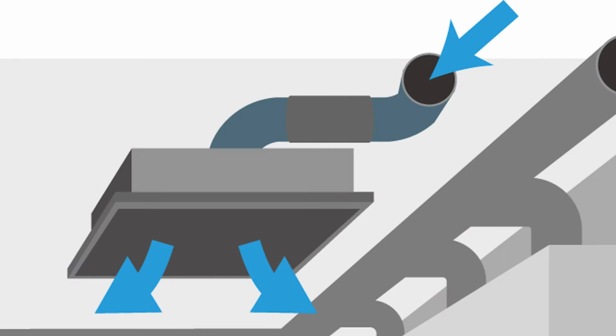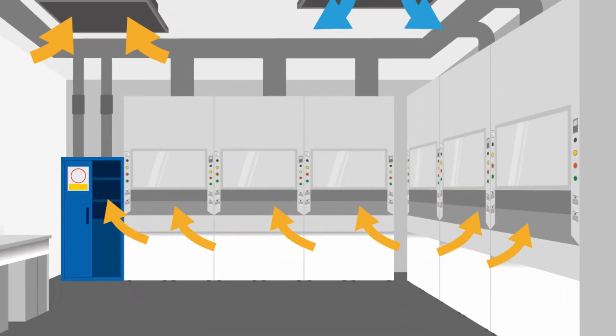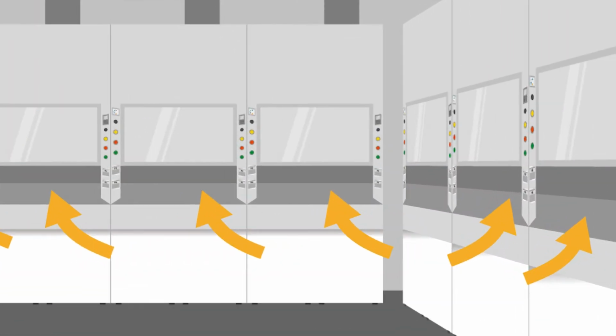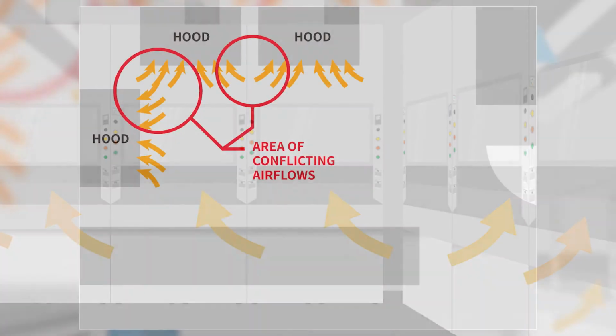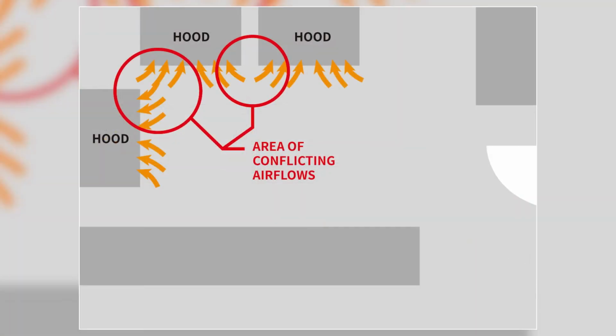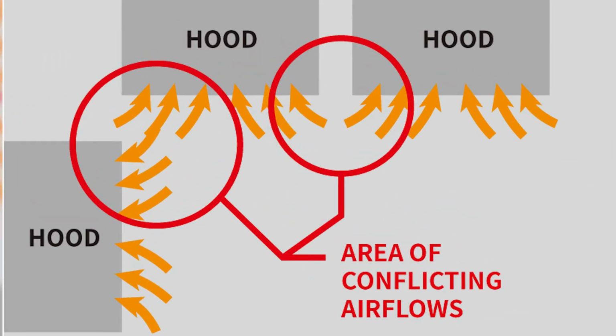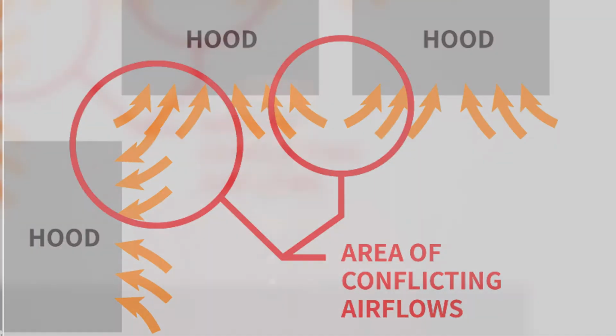Another source of turbulence is cross drafts. The most common cross drafts are caused by high velocity supply air registers being too close to the face of the hood. Also, when we have hoods too close to the door or too close to each other, there can be cross drafts. The magnitude and direction of the cross draft determine the potential impact on the fume hood's ability to contain. Turbulence is a primary factor in the loss of containment. Reducing turbulence can help the fume hood better contain.